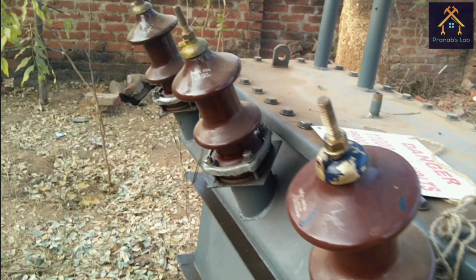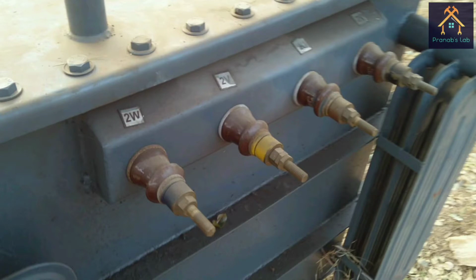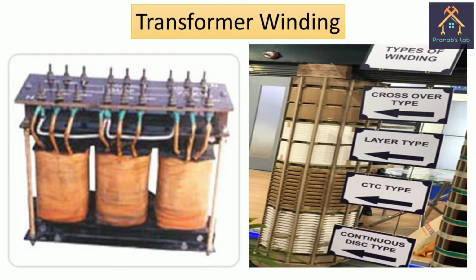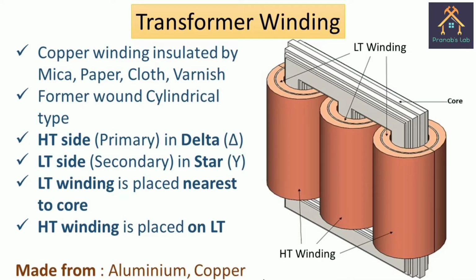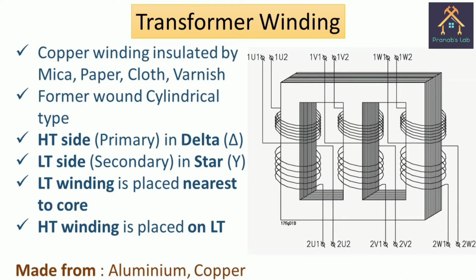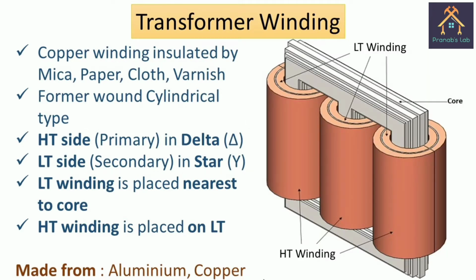The high tension and low tension terminals are internally connected with the high tension and low tension windings of the transformer. The former wounds 3-phase windings are placed on the limb of the core. The high tension and low tension windings are placed on the same limb so that it consumes less space and gives better flux linkage between the windings. The high tension windings require more insulation, whereas the low tension winding requires less insulation. So, the low tension winding is placed nearest to the core and the high tension winding is placed over the low tension winding for better insulation.